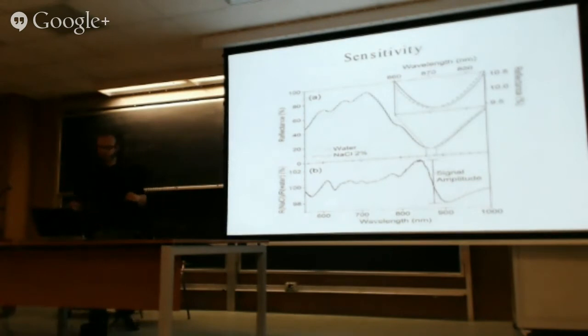So you don't measure the shift in wavelength? Yes, we measure it. It's quite sensitive here. Yes, 10 to the minus 6. We arrive at 10 to the minus 6, and the problem is that you start calculating the fluctuations that come in the refractive index from the fluctuation of temperature. So if you want to go further, you need a cryostat, you need to control pressure, you need to control temperature. But here we want just to make measurements at room temperature and at room pressure.